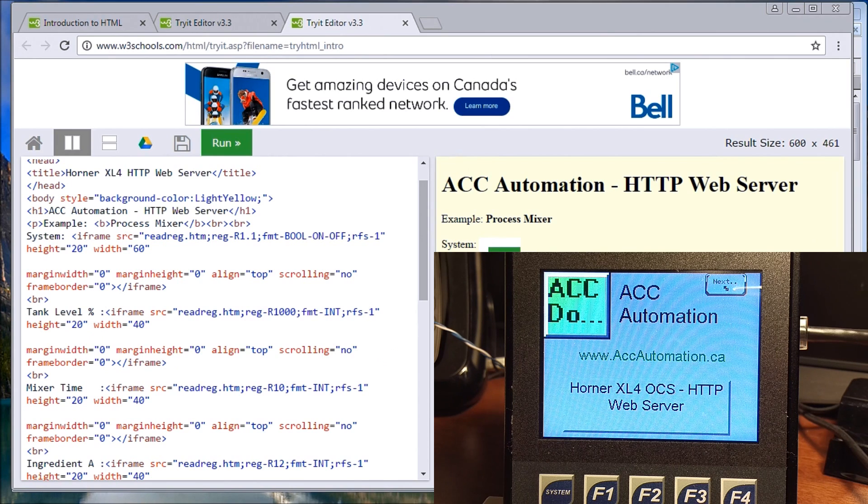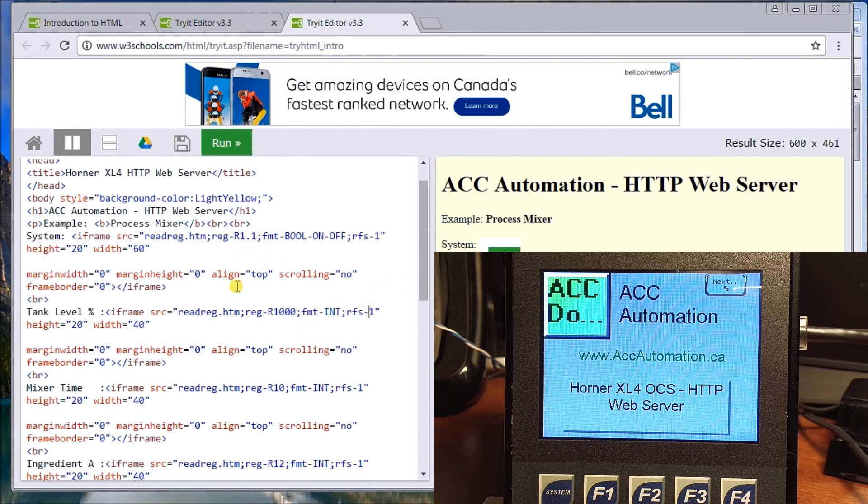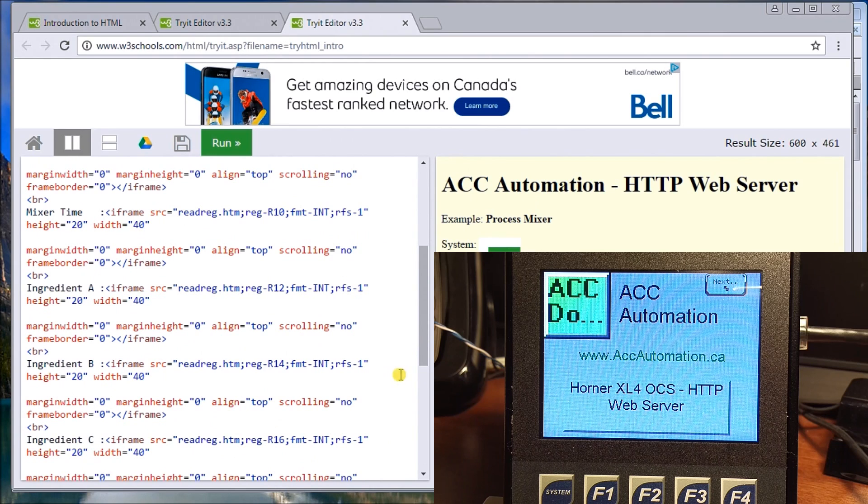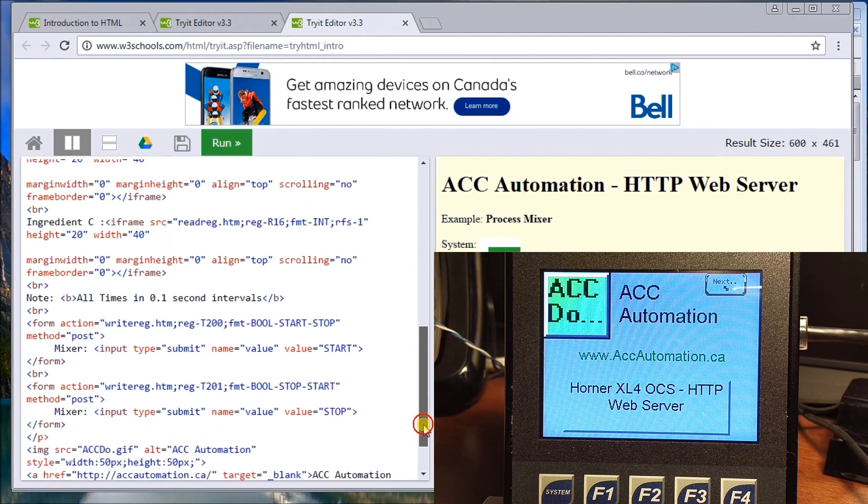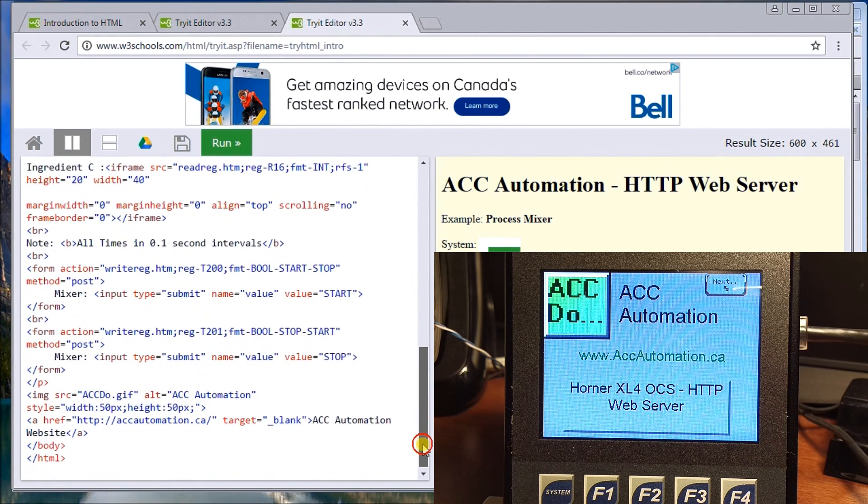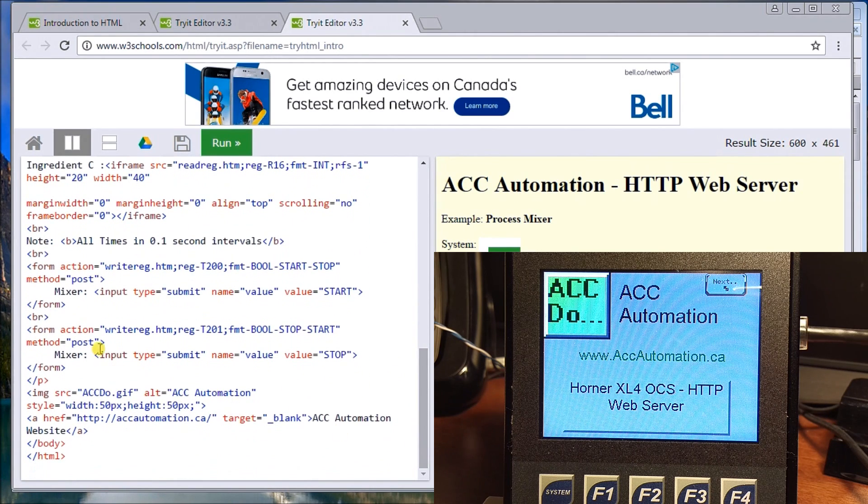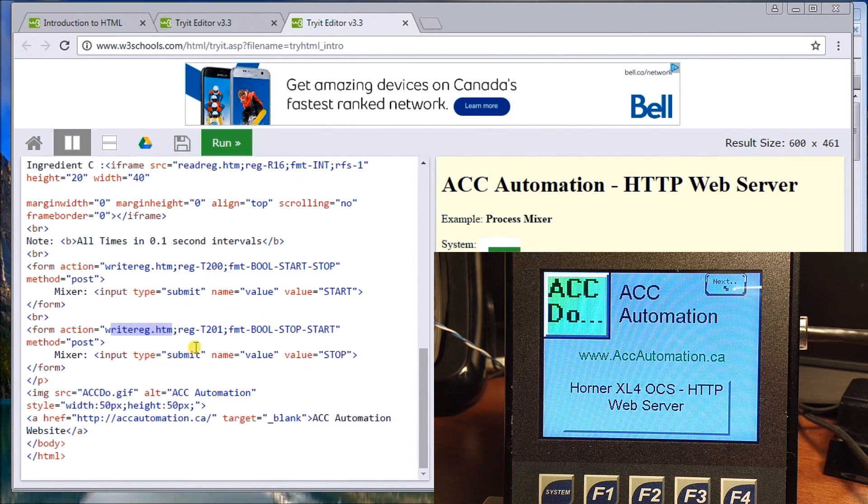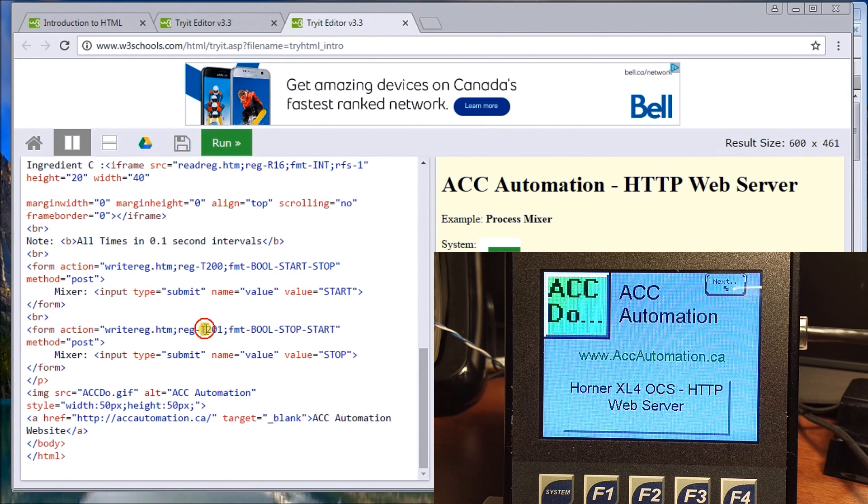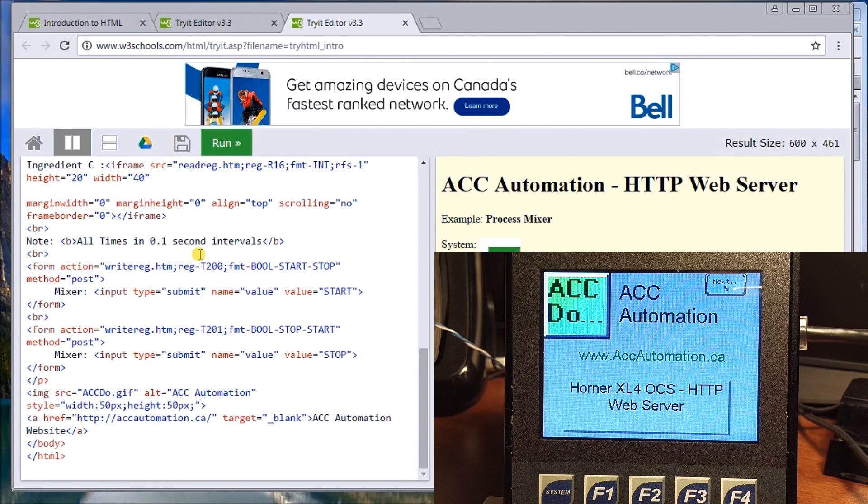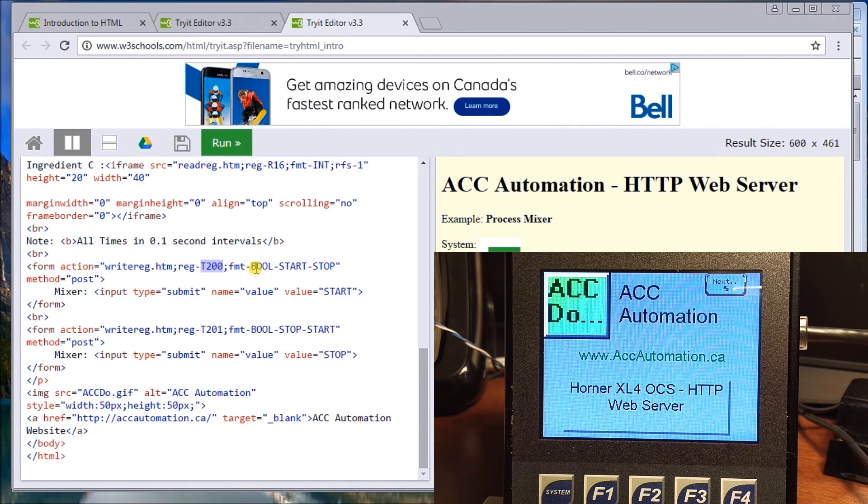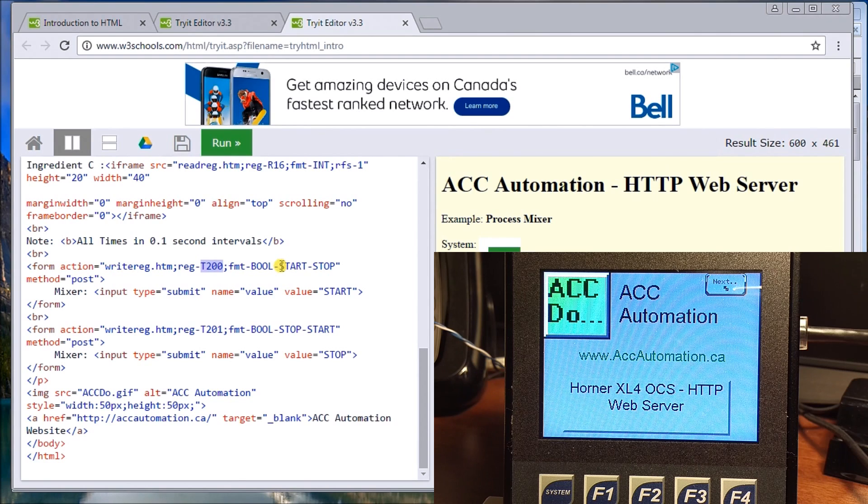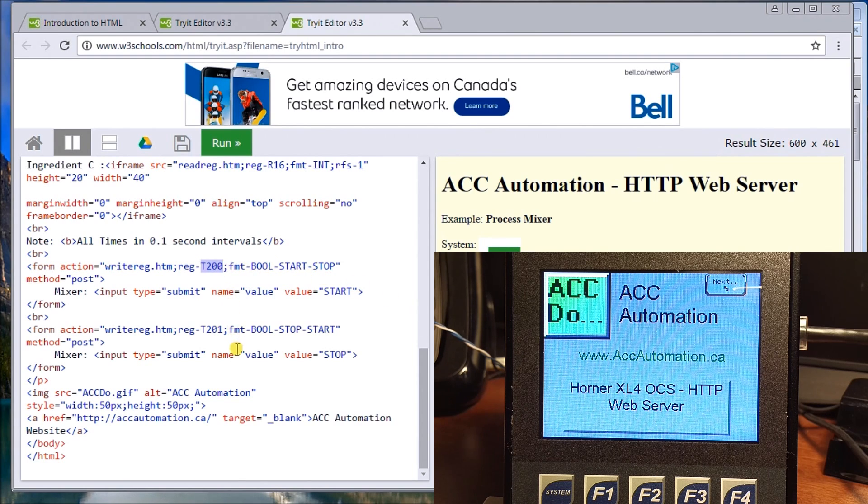For writing information, you see here we have mixer start, mixer stop, and that takes the place of what they call a form. So you have form action and then here we put write.htm and what we're going to write to is temporary bit T201 to stop. My start is right up here, T200, and it's a boolean expression. The labels are going to be start and stop for the mixer and error for the starting sequence.